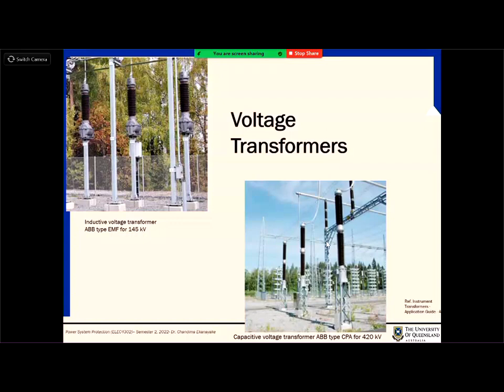3 minutes to go through the voltage transformers, right? I'll quickly go through them. It's again the same as CTs, but what you are doing is reducing the voltage from primary to secondary. In real life, voltage transformers are columns, but unlike the CTs, which had 2 connections, in the voltage transformers you will have only 1 connection, here on the top. The other end is connected to the ground.